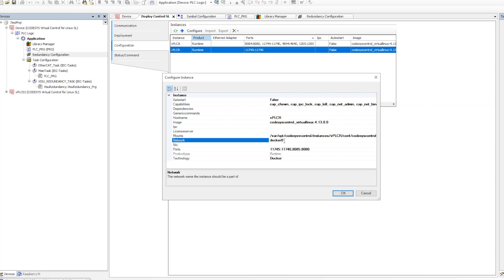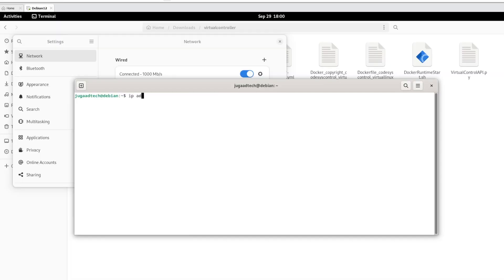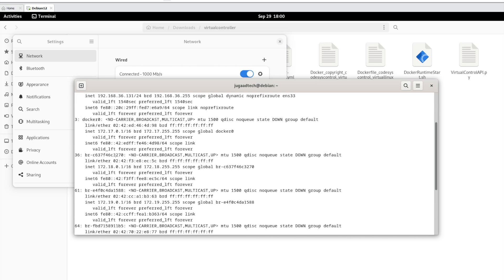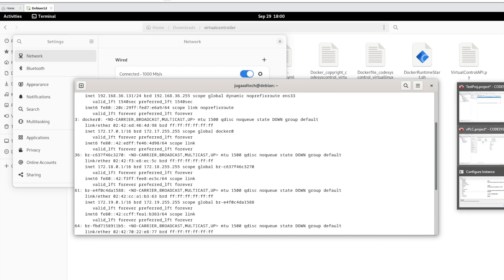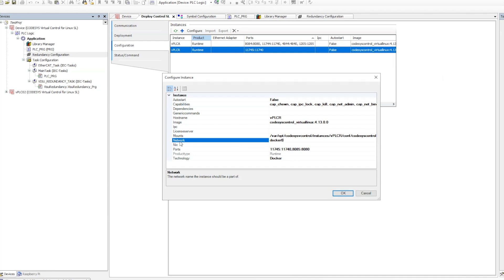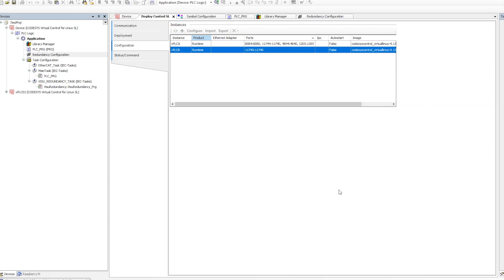Now let's look at how the networking works for virtual PLCs. Going to the Deploy configuration, in the 'Network' section I am providing the network name. I got this network name from the virtual machine — when deployed, it created multiple networks. We need to select exactly which network to bring the PLC onto. The key point is that to make PLCs redundant or communication-enabled, both PLCs must be on the same network.